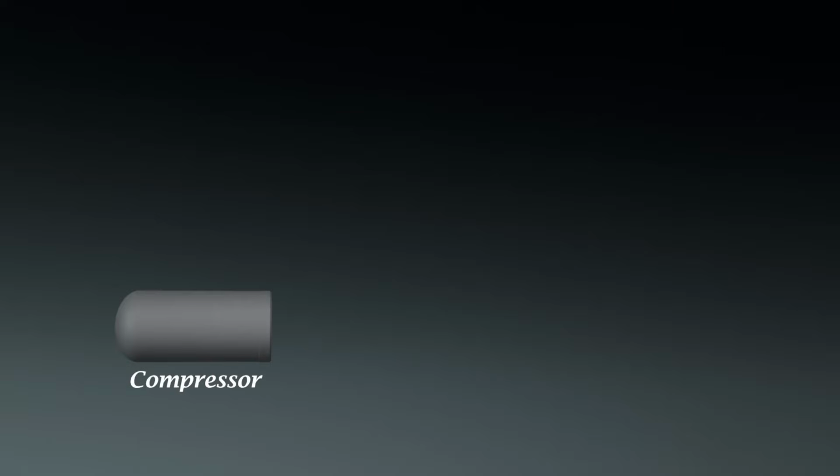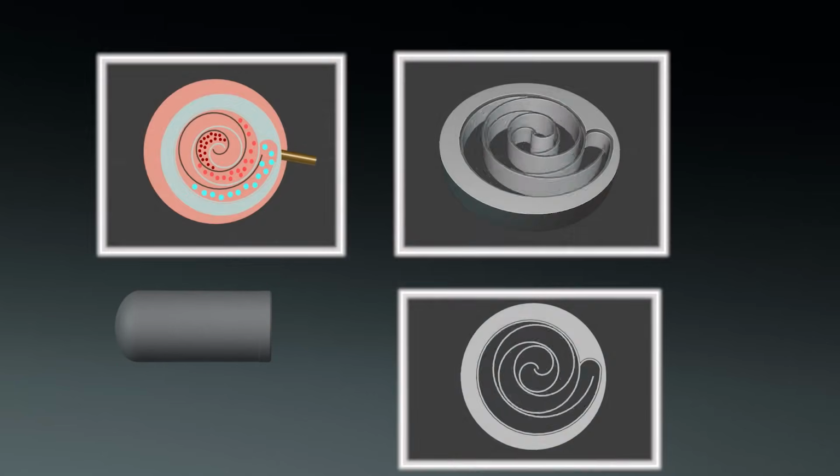The cycle begins with the compression of the refrigerant in the compressor. This is a scroll type compressor. In scroll compressors, there are two spirals. One is static and the other orbits inside it to compress the refrigerant. High pressure and high temperature refrigerant exits the compressor.